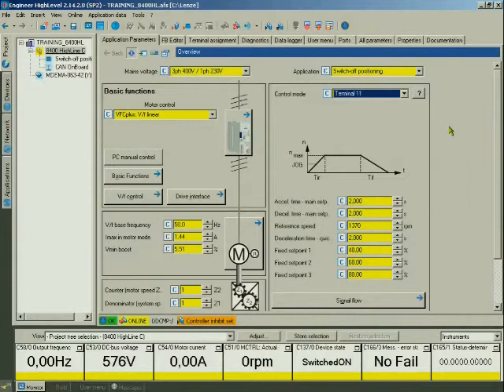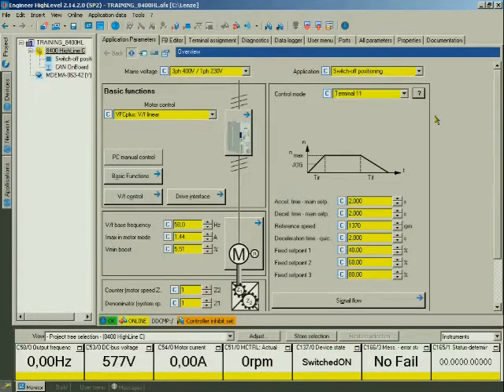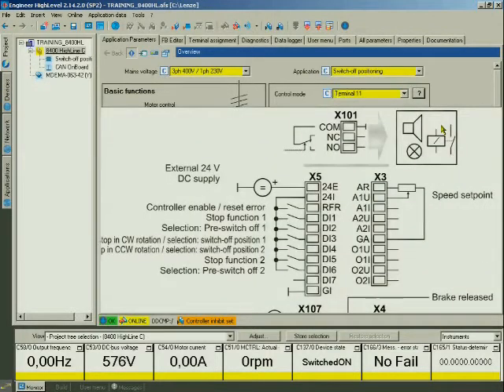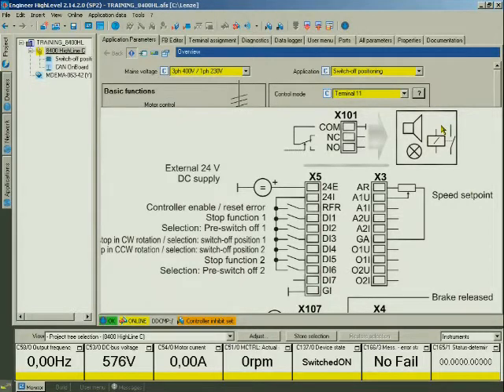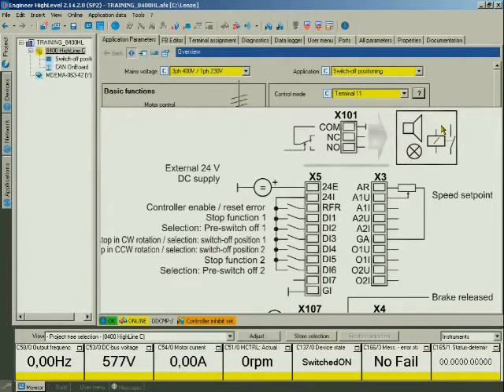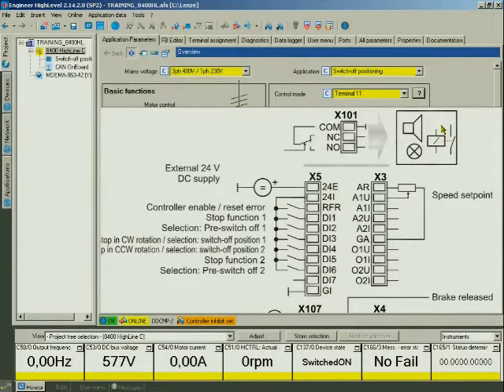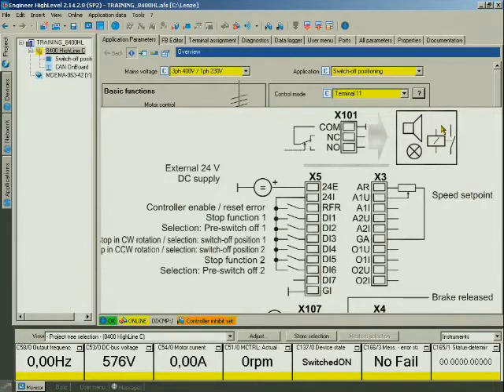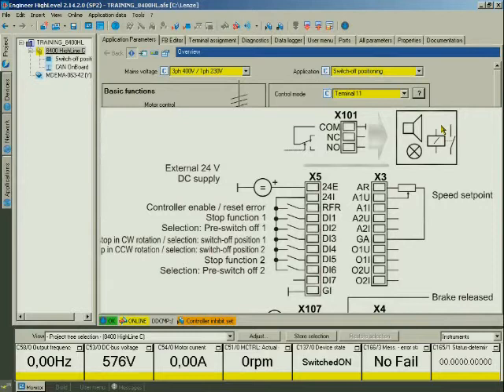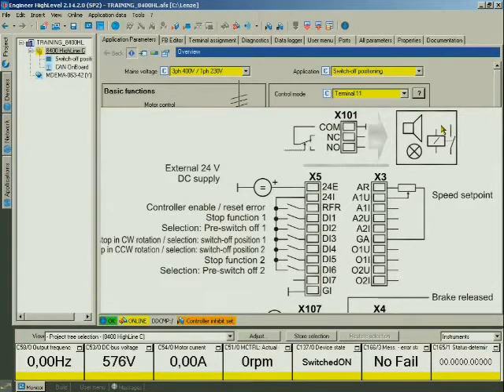When we click the question mark, we see the terminal assignment. Control mode terminal 11 pre-assigns the digital inputs in a way that the drive accelerates to normal speed. By the pre-switch-off switch pulse, it is decelerated to creep speed. The stop function switch pulse brakes the drive to standstill. Fields of application are for instance garage door drives.